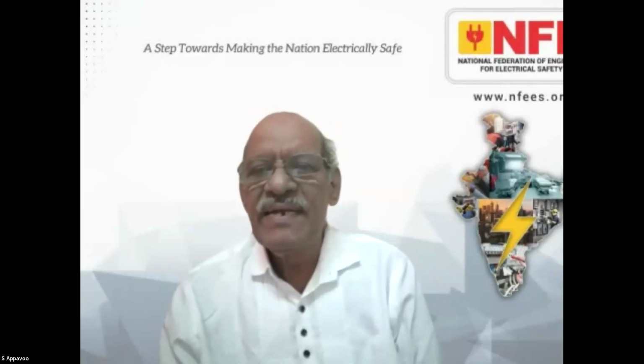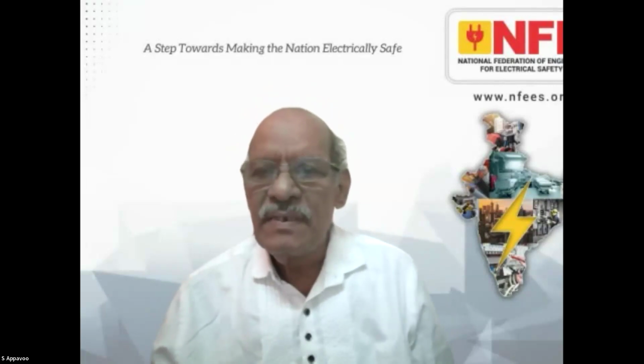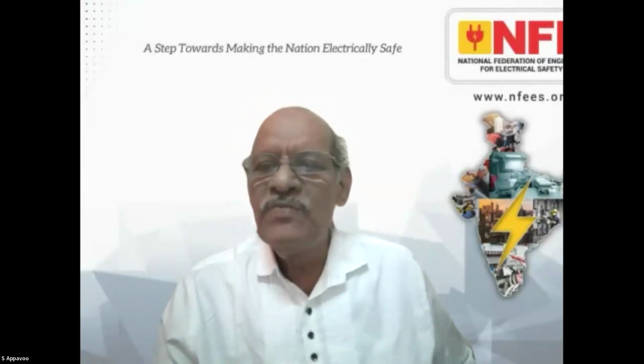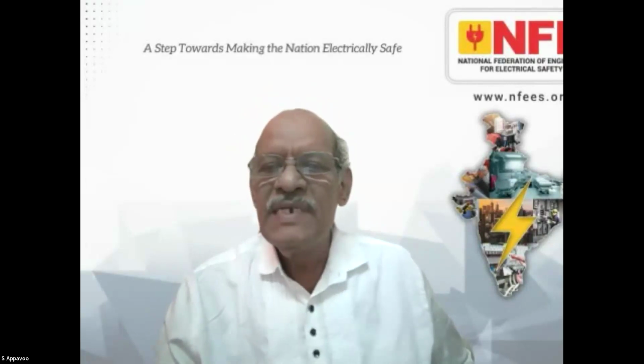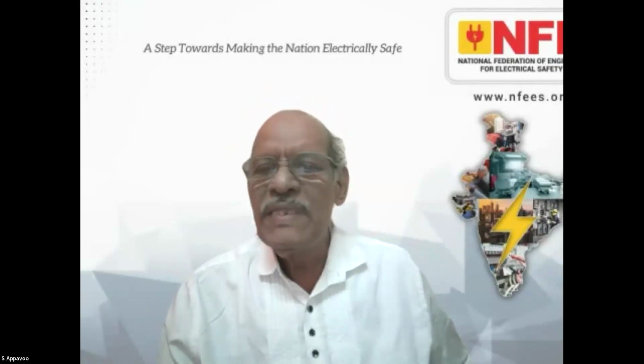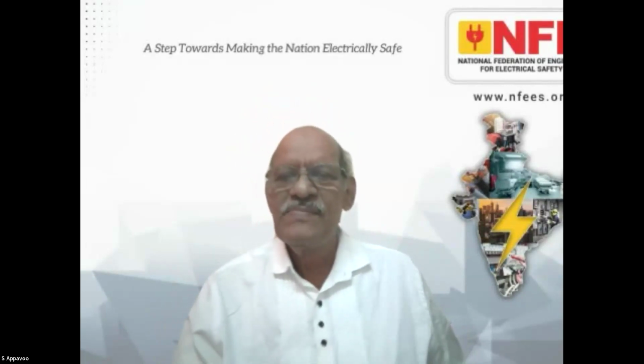One more question, from Davis AR. In the case of an electrical room with HT panel, LT panel, and PLC and drive panel, can we connect all the earthing systems for bonding, including the PLC reference earthing? Actually, there are a lot of questions on earthing, and I think IS 3043, the new version, needs to be released fast. But yes, you are supposed to bond all those things together. The PLC earthing is called functional earthing. Functional earthing and the normal earthing, you are supposed to have referenced through one insulated conductor. So that also should be referenced to earthing at one point.